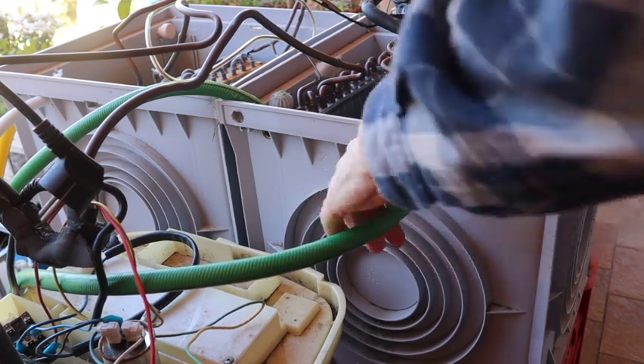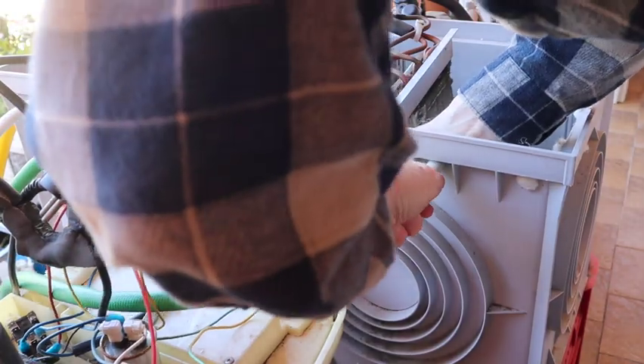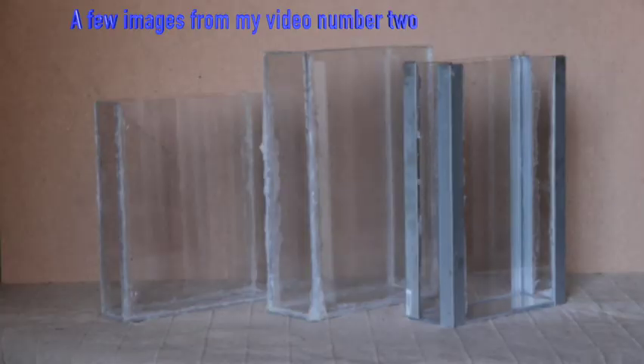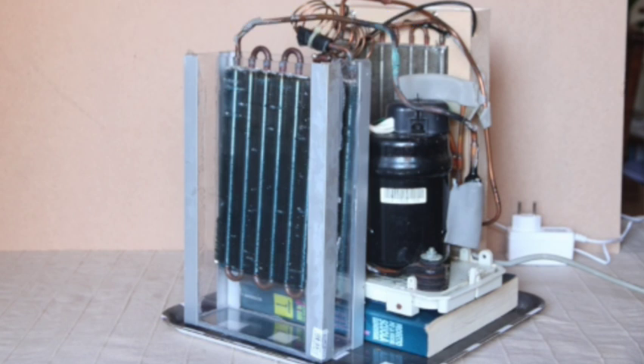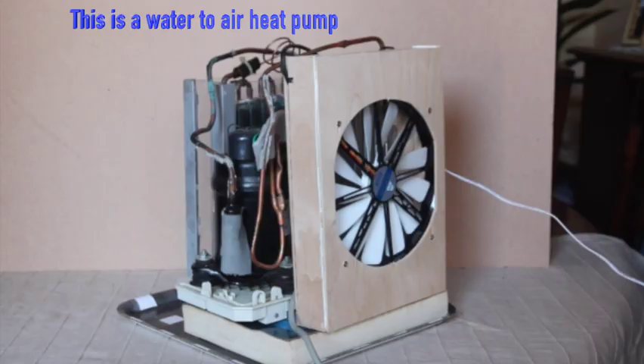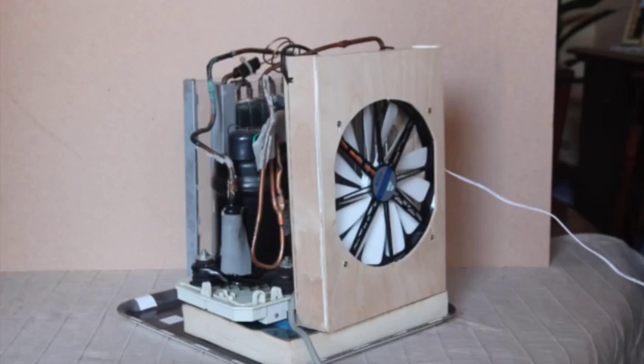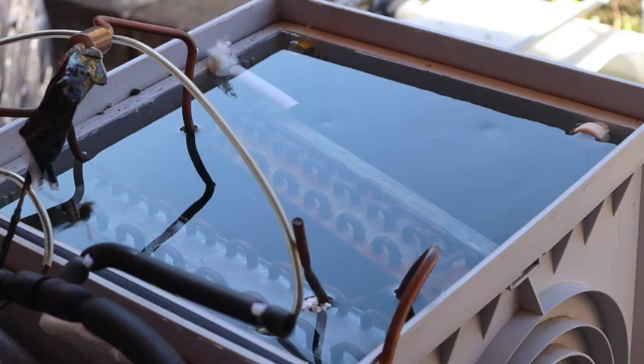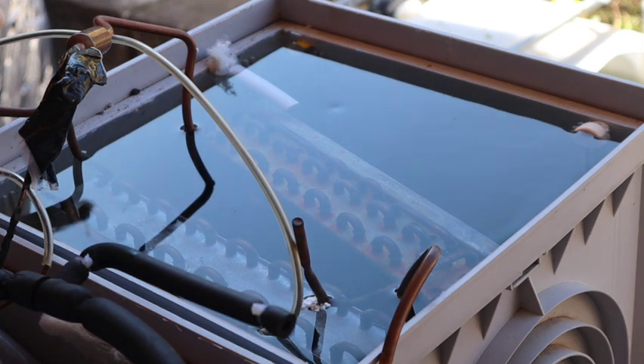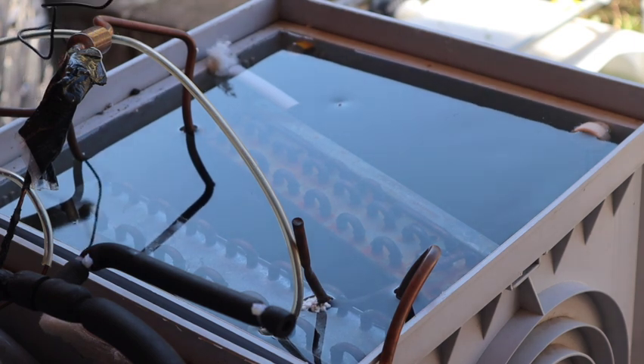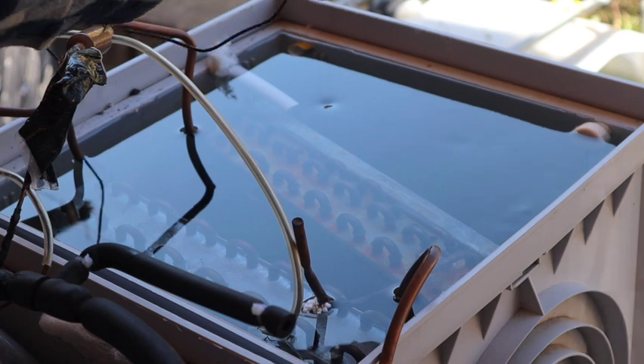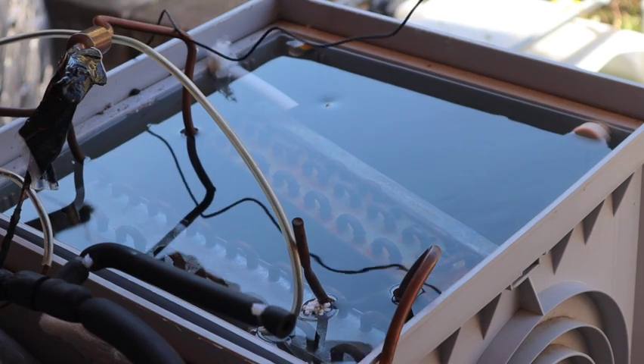A custom-made water box can be more suitable for this project than what I used. The best is if transparent for easy inspection, but also because it's just cool. Compact and integrated with the compressor. The water box allows you to have modular heat pumps that you can add and switch on and off. My water boxes were open, and the system with pumps and gravity are the most reliable way to have a controlled water flow. Another way is to design a closed box around the heat exchanger that closes watertight around the copper tubes. That will be not so easy.